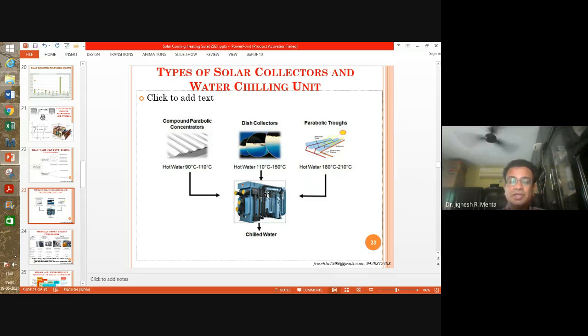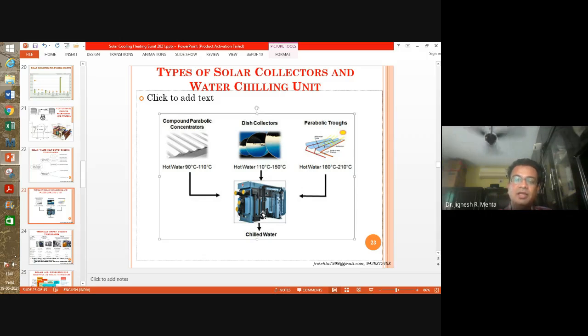Yeah. So this chilled water system can be an absorption cooling system, but again in absorption cooling you have single stage, 2 stage, and now even 3 stage systems are there. So when you want to increase the effect, single effect, double effect, triple effect. For double effect you need higher temperatures, for triple effect you need even higher temperatures. And as will be shown, the higher the number of effects that you have in your water chilling plant, the more COP you can expect.